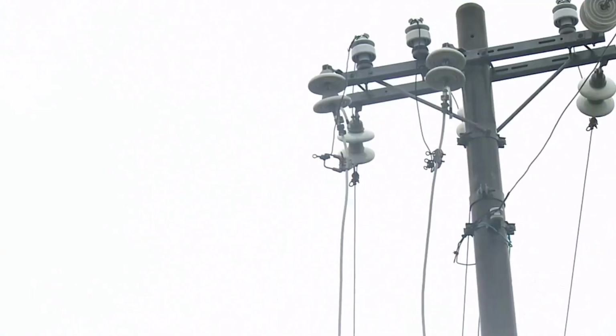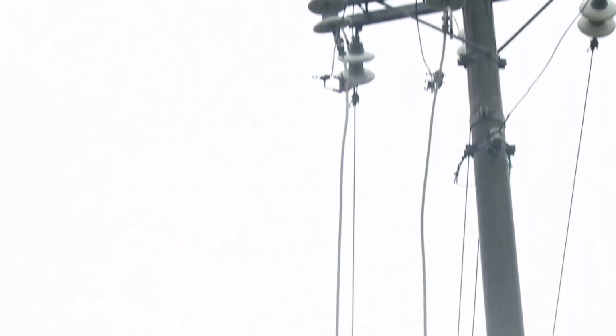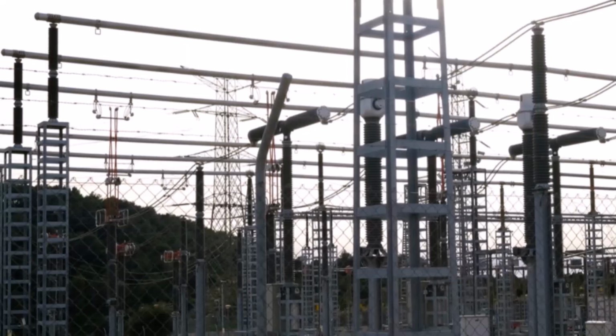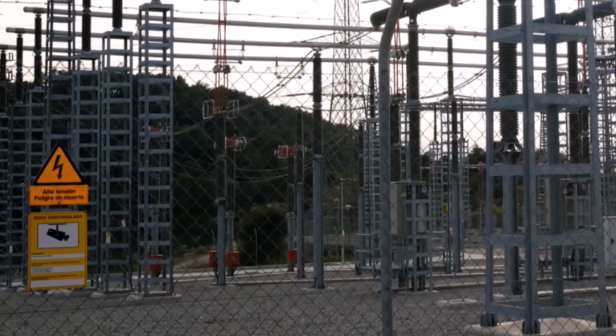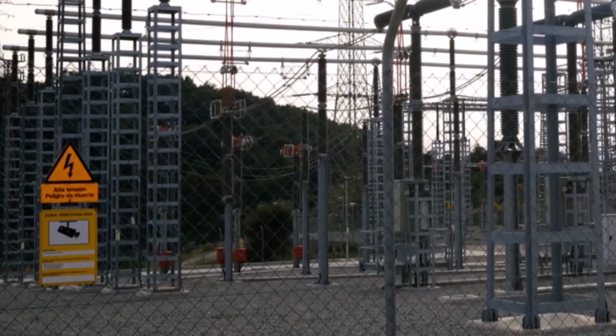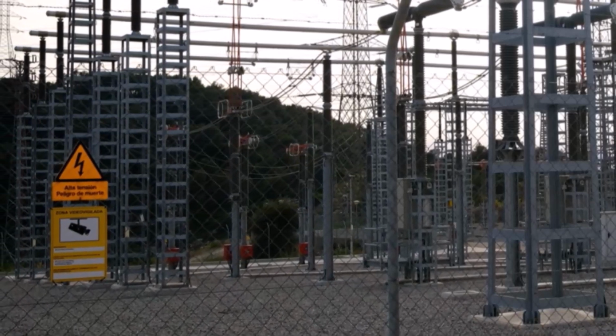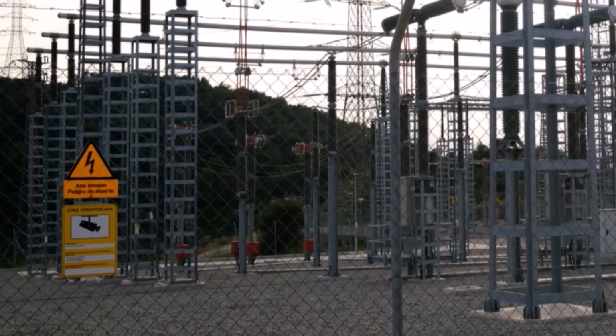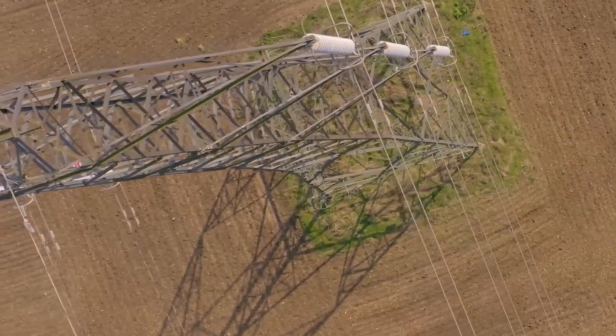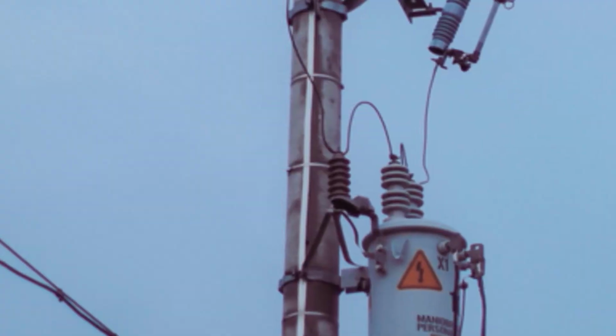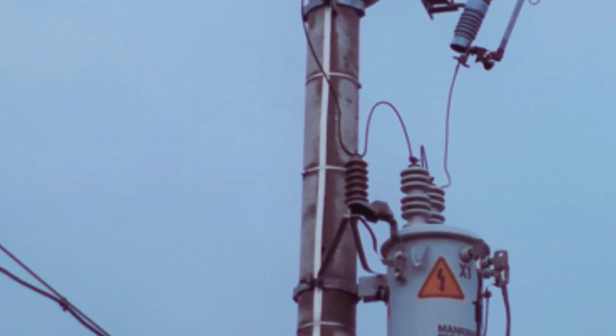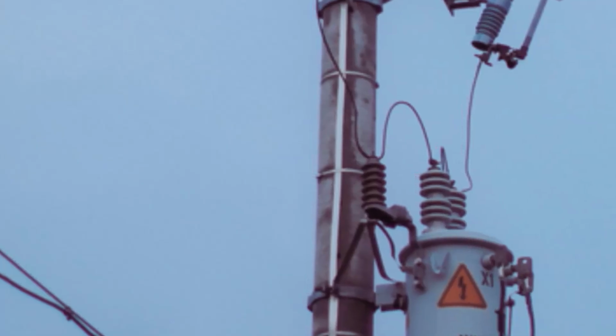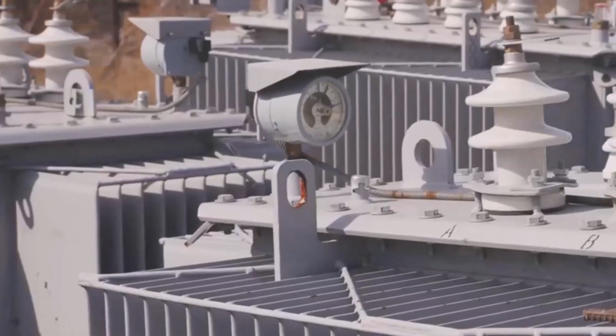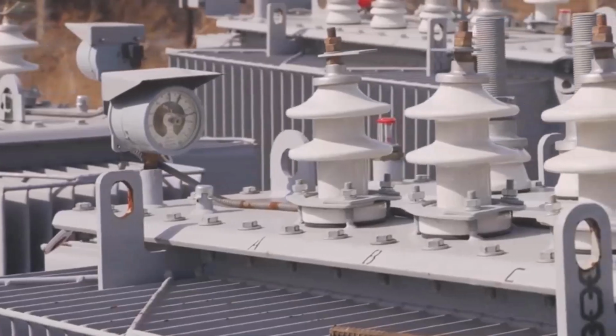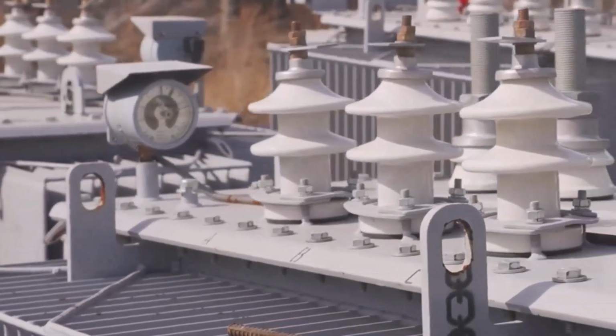Sometimes only the secondary low-voltage side of a transformer is connected in a Y configuration to provide a neutral point for local distribution. In other cases, such as in large power substations, both the primary, high voltage, and secondary windings might be connected in a Y, creating what is known as a Y-Y transformer. This is common in high voltage transmission systems. The reason Y connections are so common in transformers serving our homes and businesses is that they provide that crucial neutral point. When a transformer steps down voltage for residential use, the Y secondary gives us two different voltages.